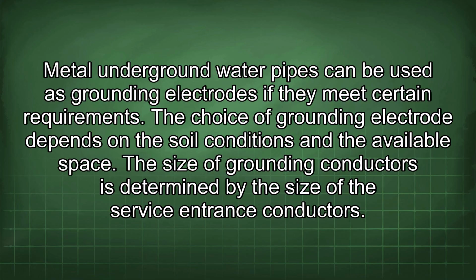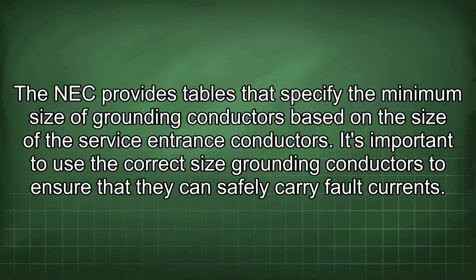The size of grounding conductors is determined by the size of the service entrance conductors. The NEC provides tables that specify the minimum size of grounding conductors based on the size of the service entrance conductors. It's important to use the correct size grounding conductors to ensure that they can safely carry fault current.